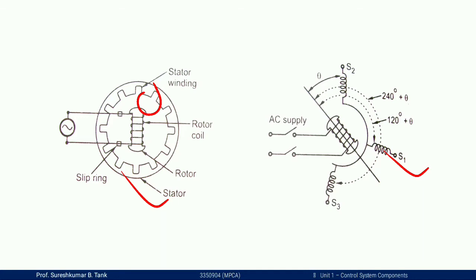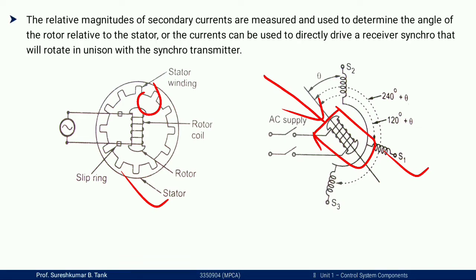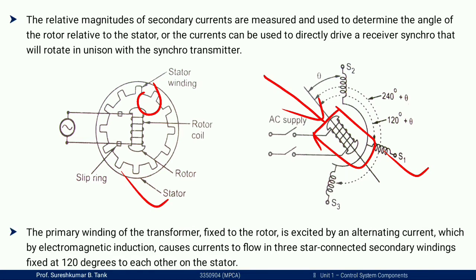These slots carry three-phase windings always connected in star configuration. The rotor also comprises a laminated core of dumbbell shape. It carries a single-phase winding. The ends of this winding are brought outboard to slip rings and two brushes. The synchro transmitter has stator windings spaced 120 degrees apart, totaling 360 degrees, with rotor winding provided to the rotor side.